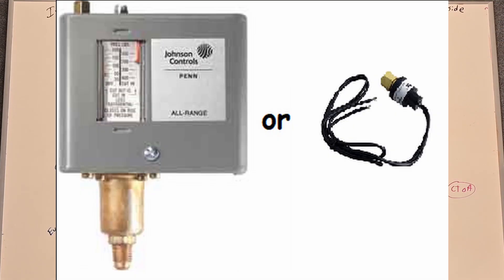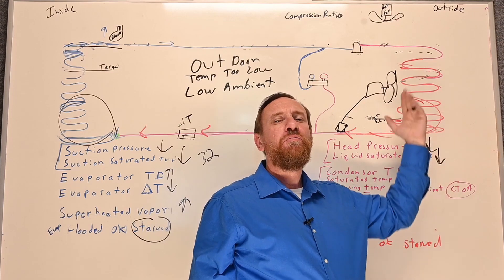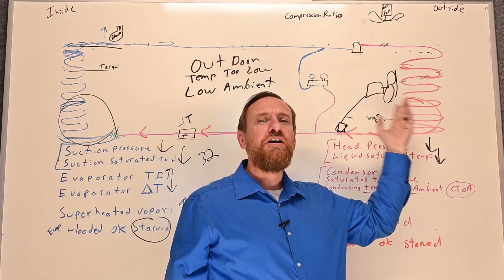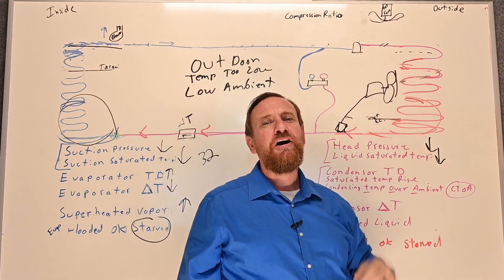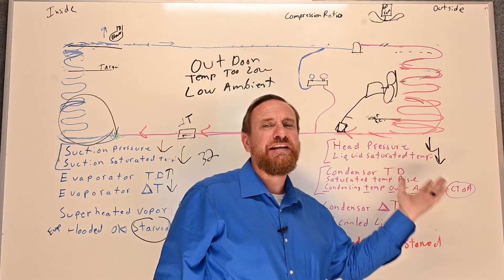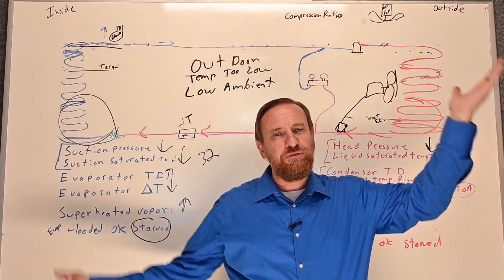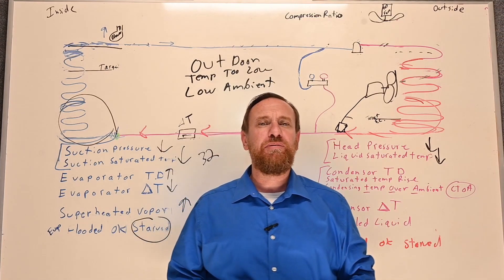It's called a fan cycle switch or a fan cycle low ambient kit. We simply cycle this fan on and off to keep the head pressure within a range. So that head pressure drops too low, we cycle the fan on and off. But there's some catches to that. As we're cycling the fan motor on and off, it's more likely for that fan to wear out from the starting and stopping. And it must be a ball bearing fan. And there's some other situations as well as the problem is having that big swing between the fan coming on and off, which puts some work on the compressor, that swing between up and down. So it is one of the methods, but it's not the most appreciated method.